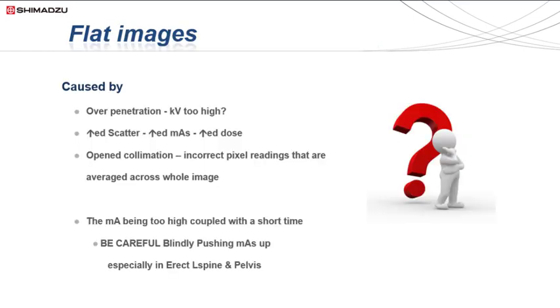So what can be done about the flatter looking images? Keep in mind that the programming of image settings plays an important role here. Protocols may have been purposely programmed to appear flatter to align to preferences from reporting radiologists. But if this is not the case and intermittent images appear flat and grey, this can be caused by overexposure. Traditionally, high KVs on film screen would yield a flat, low contrast image due to latent scatter detection.